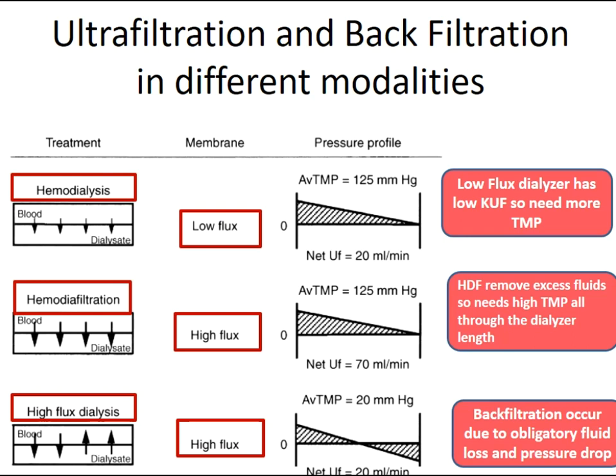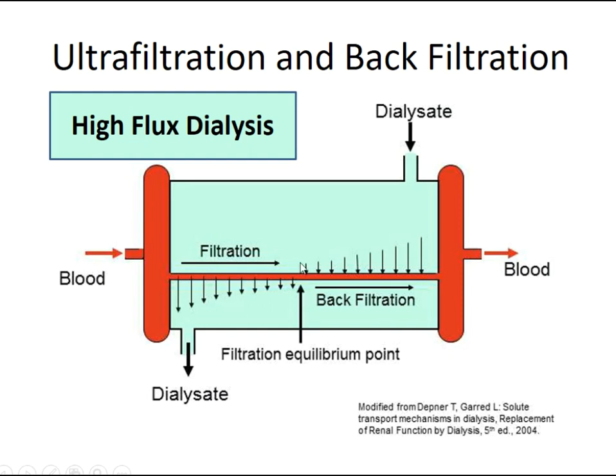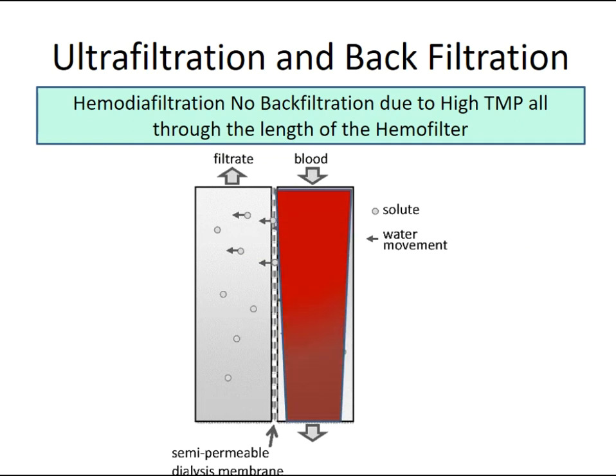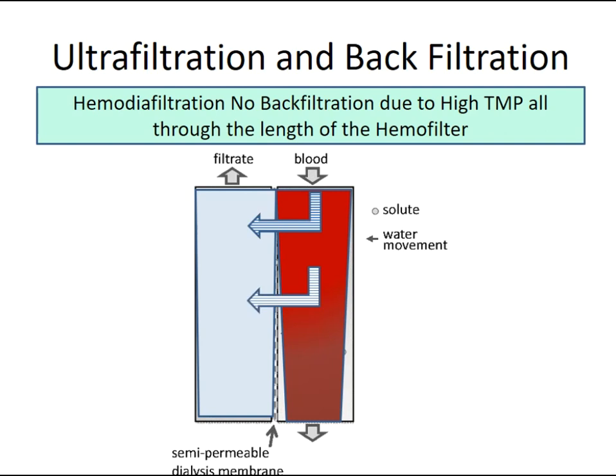Back-filtration occurs only in high flux dialysis, due to obligatory fluid loss and pressure drop. In the middle of the dialyzer there is a filtration equilibrium point: filtration happens in the first part from the blood side toward the dialysate side, and subsequently a pressure drop — with higher pressure in the dialysate — causes back-filtration. In hemodiafiltration, no back-filtration occurs due to high transmembrane pressure throughout the entire length of the hemofilter, so water moves from almost the whole length of the dialyzer.